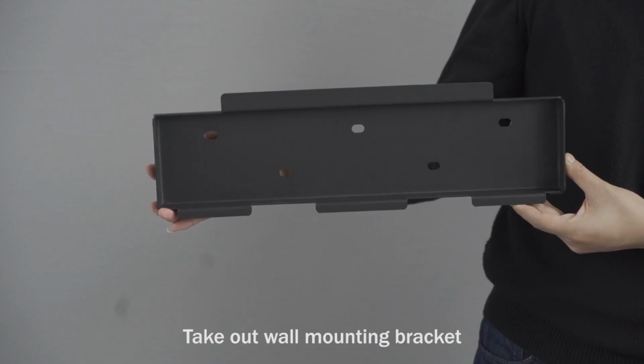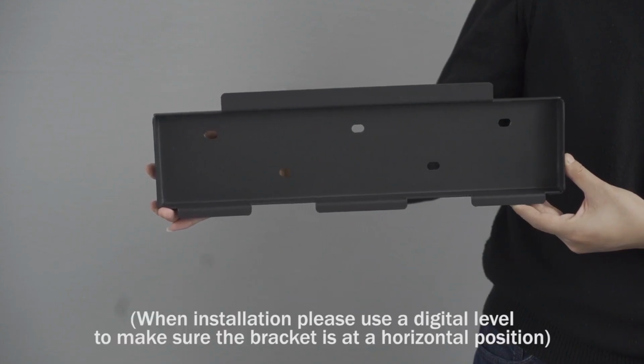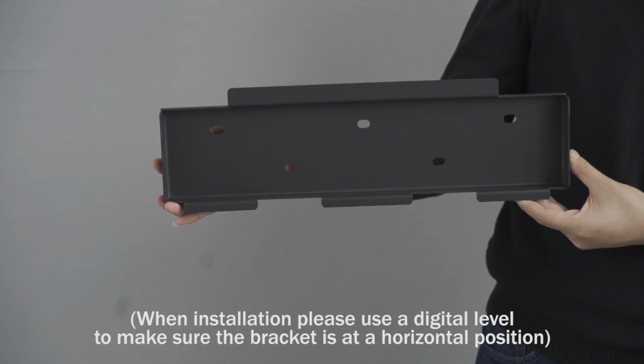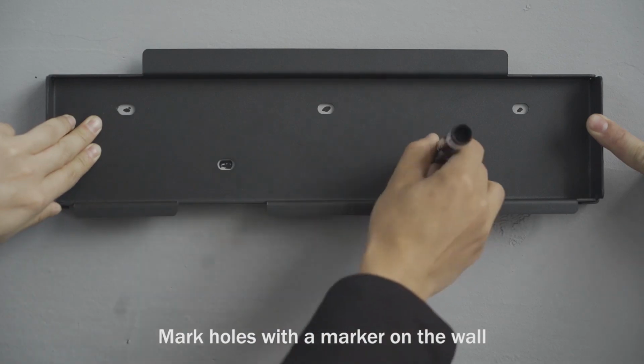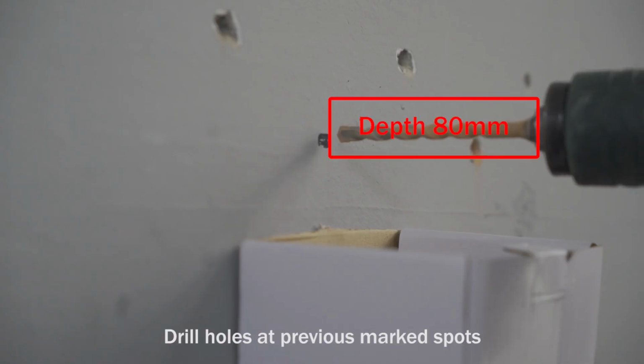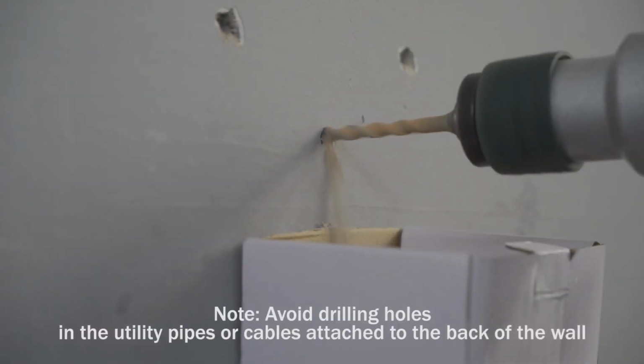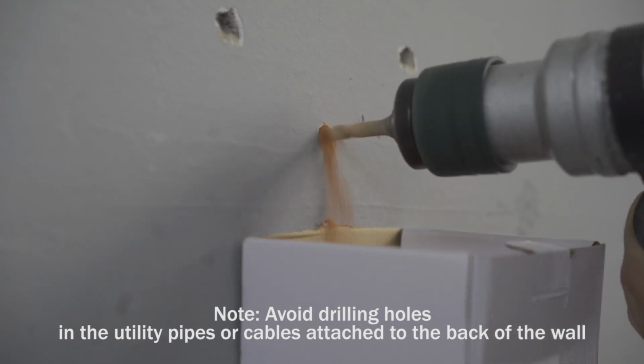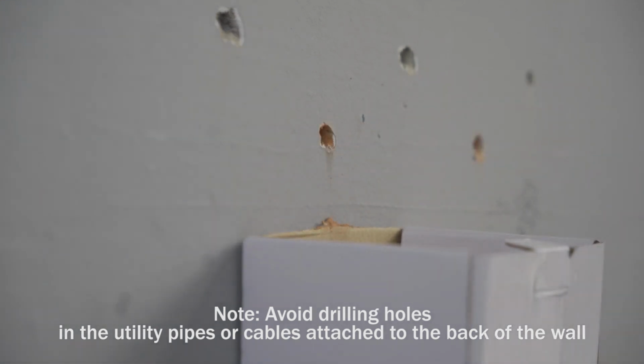Take out the wall mounting bracket. When installing, please use a digital level to make sure the bracket is in a horizontal position. Mark holes with a marker on the wall. Drill holes at the previously marked spots. Note: avoid drilling holes in the utility pipes or cables attached to the back of the wall.